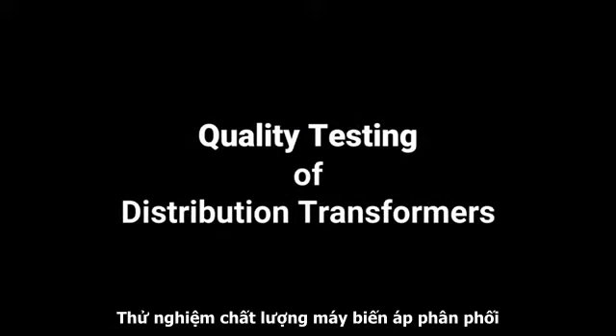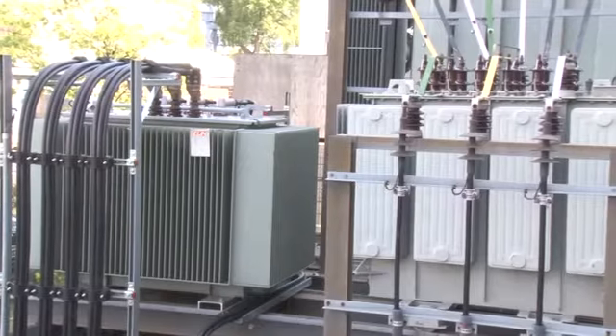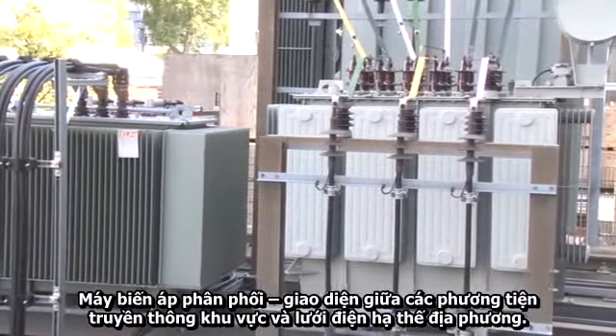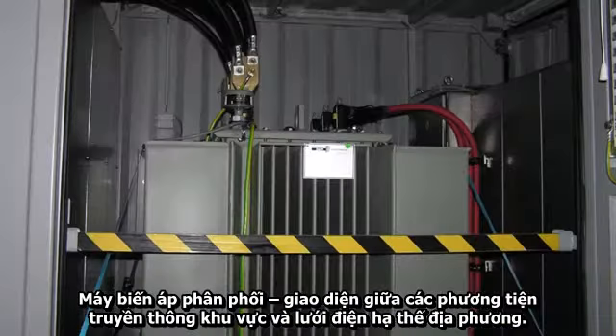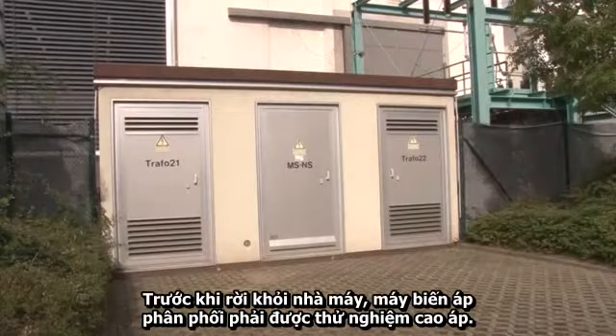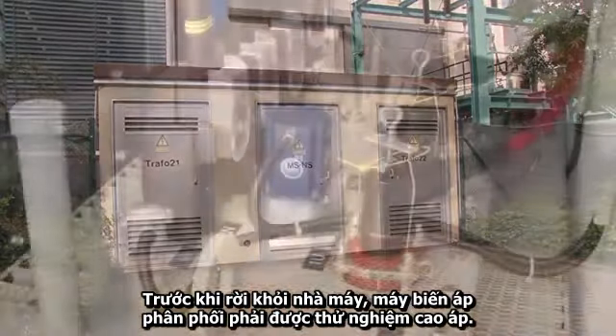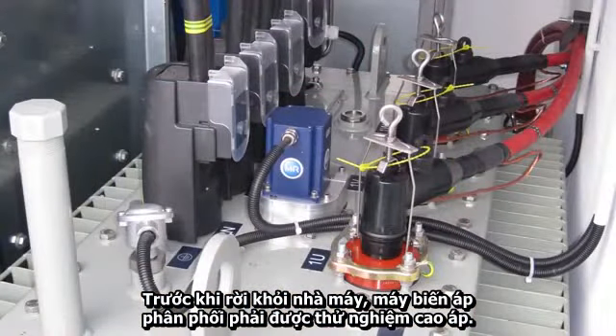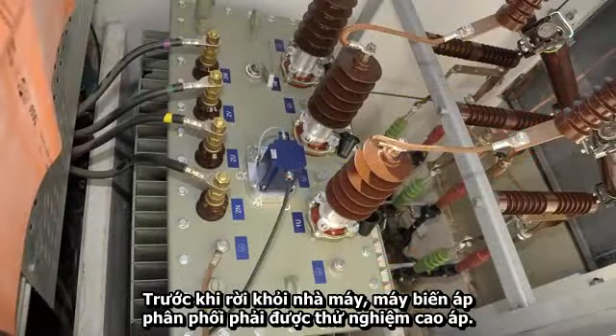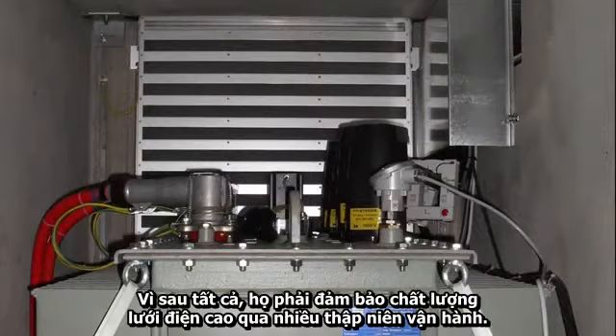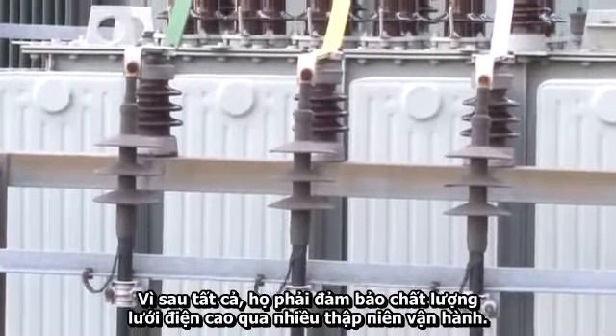Quality testing of your distribution transformers. Distribution transformers are the interfaces between regional medium and local low voltage grids. Before leaving the factory, the distribution transformers must undergo comprehensive high voltage tests. After all, they must later guarantee a high grid quality over many decades of operation.